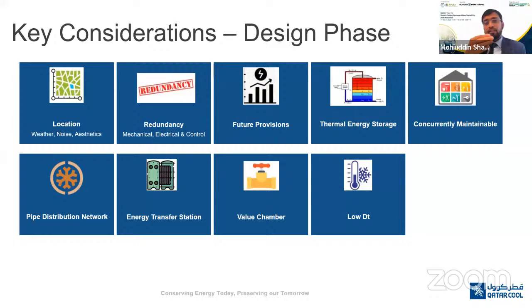Also, if this happens during the peak summer season, your additional capacity would be required. That means if you have designed a plant for 30,000 TR, you might not be able to take 30,000 TR out of that plant at all. It would be significantly less depending on what the return water temperature would be. So during the design stage itself, adequate provisions have to be built in. Although the problem originates from the customer side, there are measures which could be taken while designing the PDN as well as the plant to mitigate to a certain extent so that your customer service would not be compromised. Although in all the cases there would be additional cost of operation, the serving of the customer is also important.